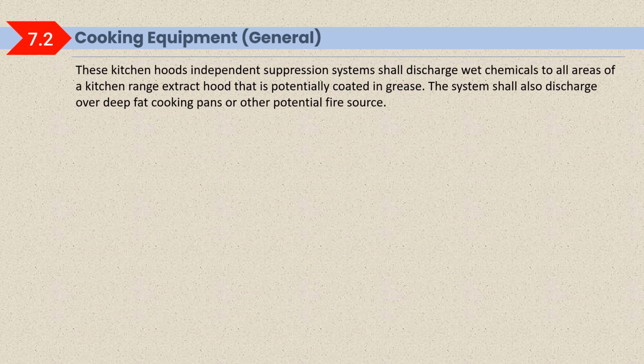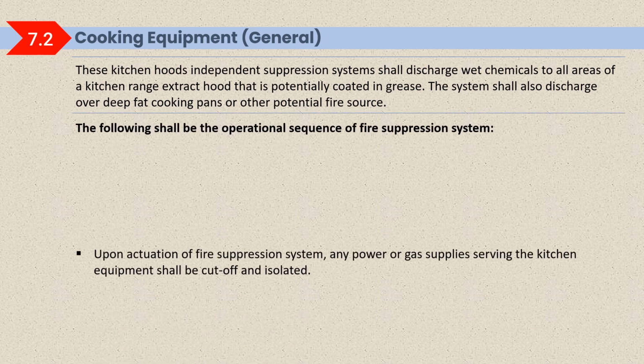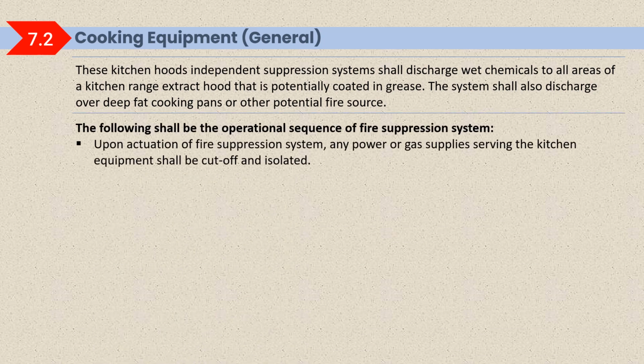These kitchen hoods' independent suppression system shall discharge wet chemical to all areas of a kitchen range and extract hood that is potentially coated in grease. The system shall also discharge over deep fat cooking pans or other potential fire sources. The following shall be the operational sequence of the fire suppression system.